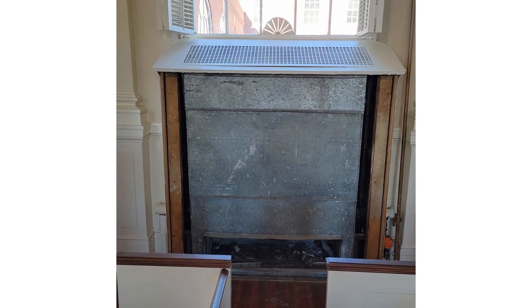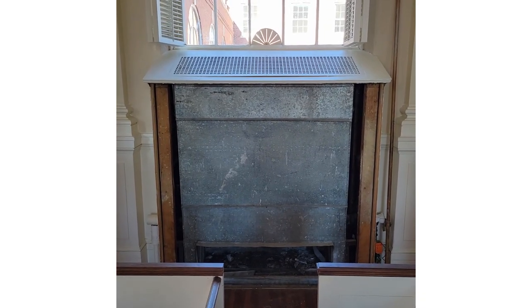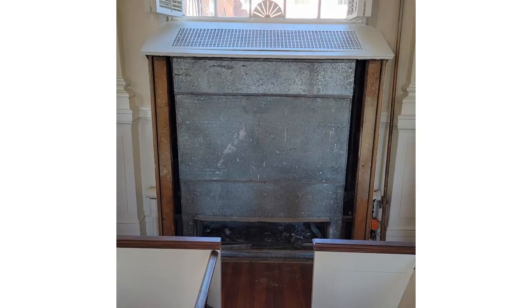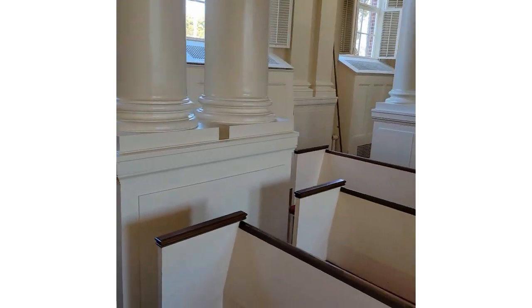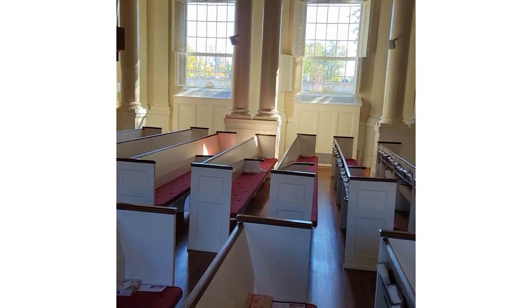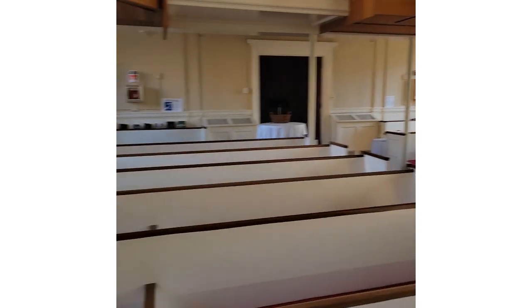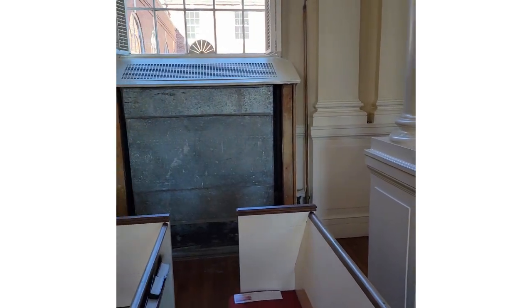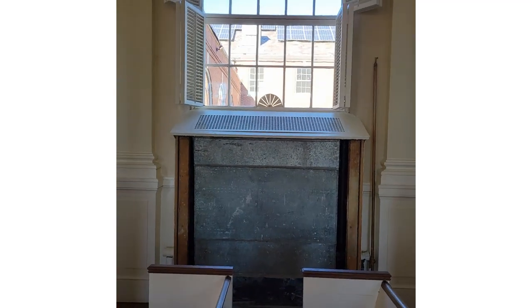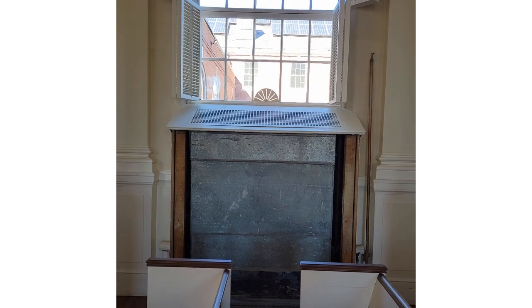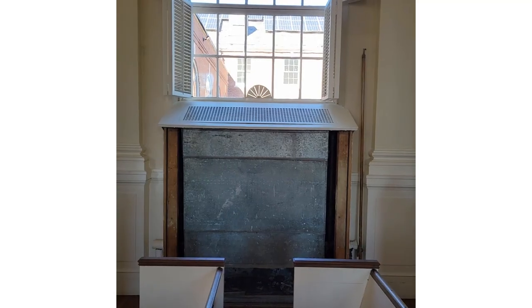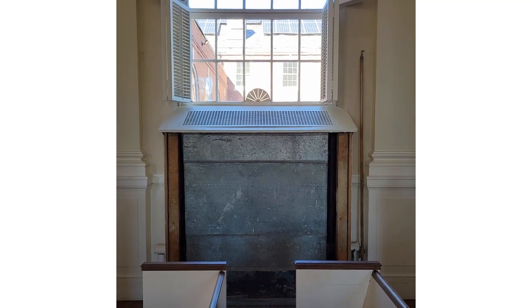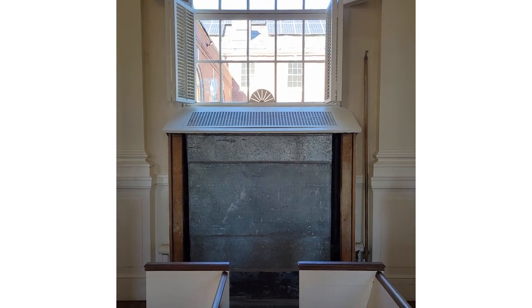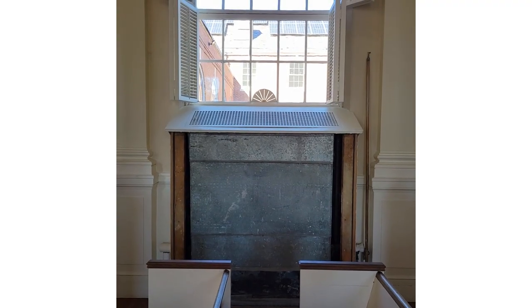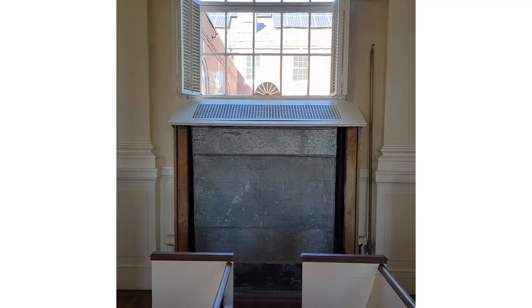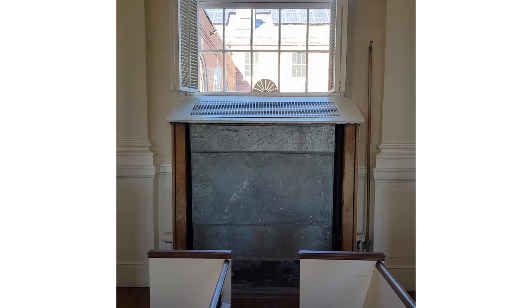So I'm in the sanctuary now, and I'm shooting this to give you an idea of the detail that went into the design and planning of the geothermal system. This is one of the radiators. You probably know in the sanctuary, pan over to the other side, they're under the windows and they're in enclosures. Well, in the design of the geothermal system, the engineers did a very thorough analysis of when we use the building, and how much heating is required. The geothermal system will use the radiators and forced hot air in the heating mode. And it was determined that to most efficiently heat the sanctuary, we need better airflow through these radiators. So all of our radiator cabinets will now have a fan, a quiet fan.